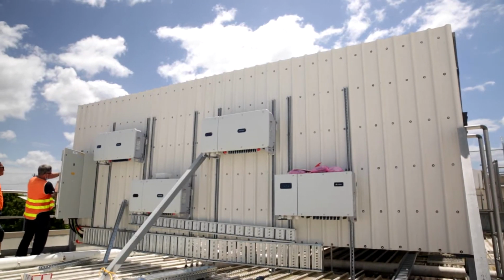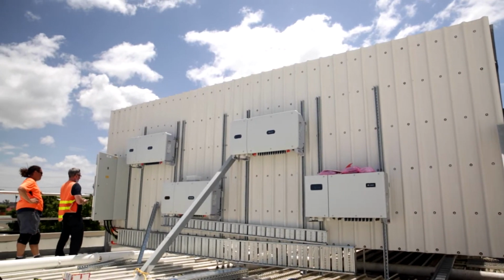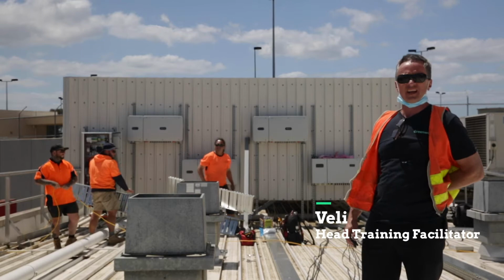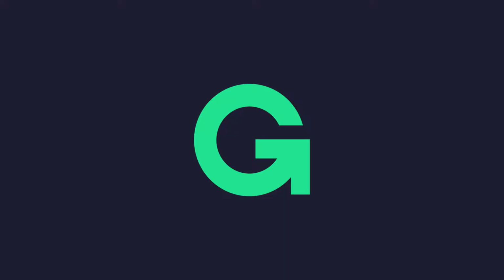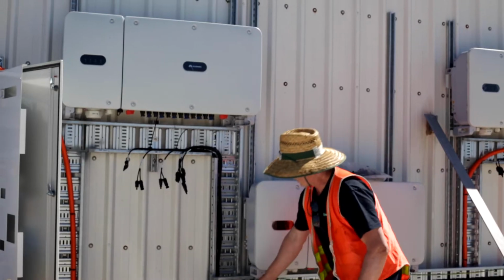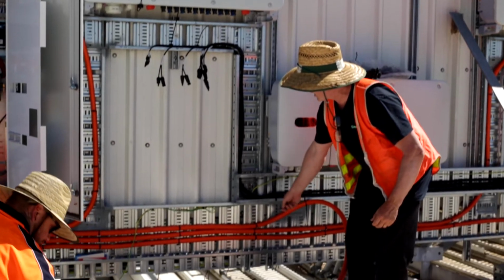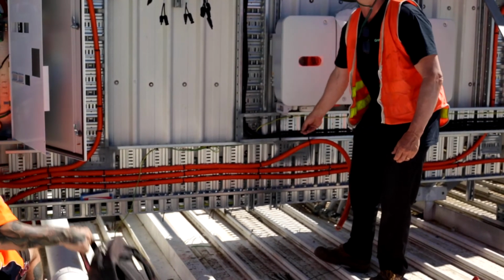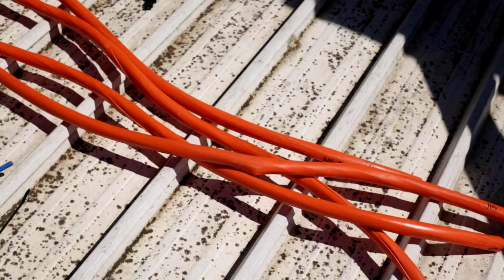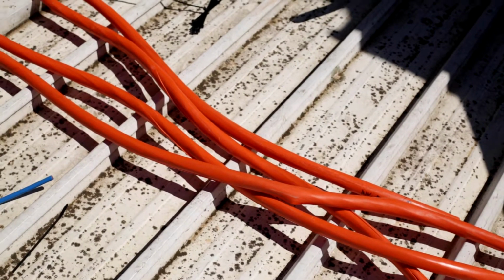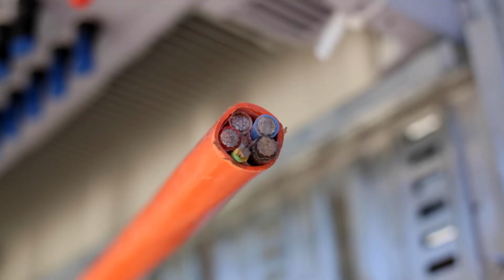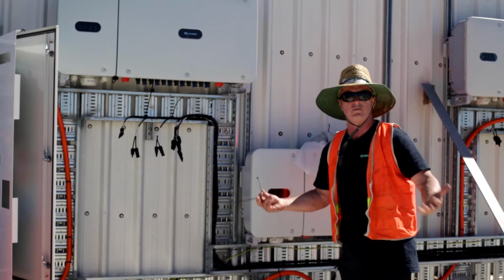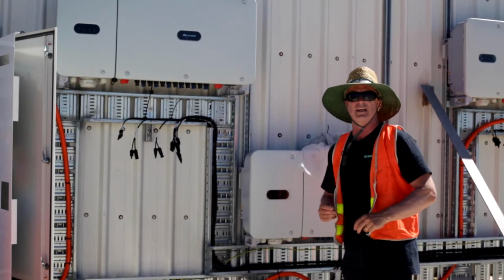So we're at inverter station number 2, and the guys at the moment are just getting ready to do a few things. So we look at the cable tray here, and this is the various 4-core and earth cables from each inverter, 35mm. The reason for that particular cable is all part of obviously your volt rise calculations.